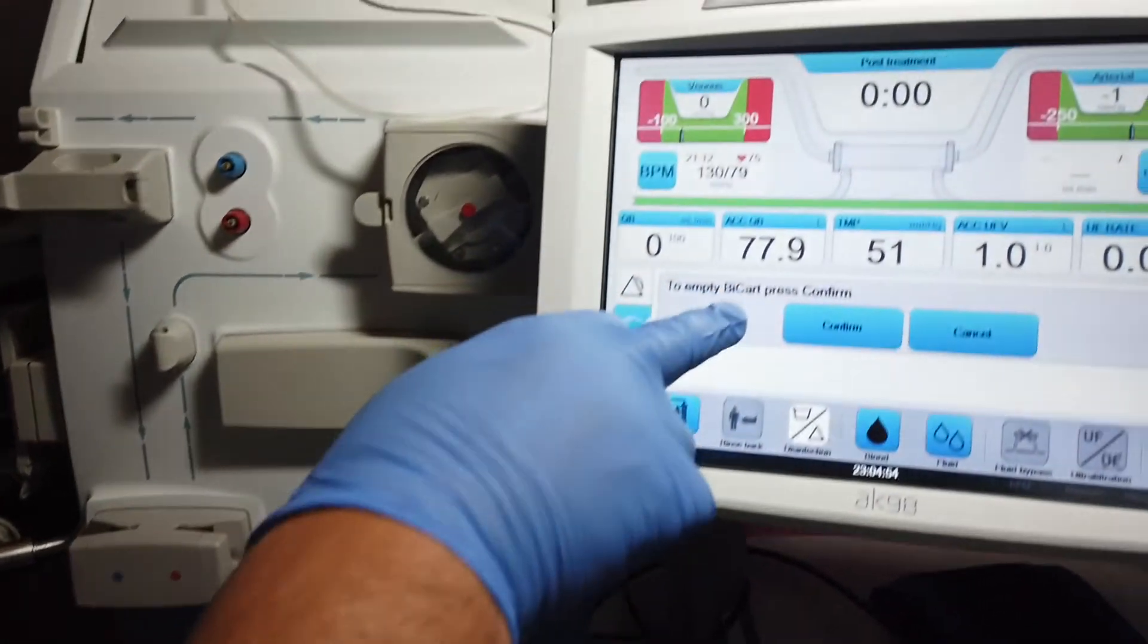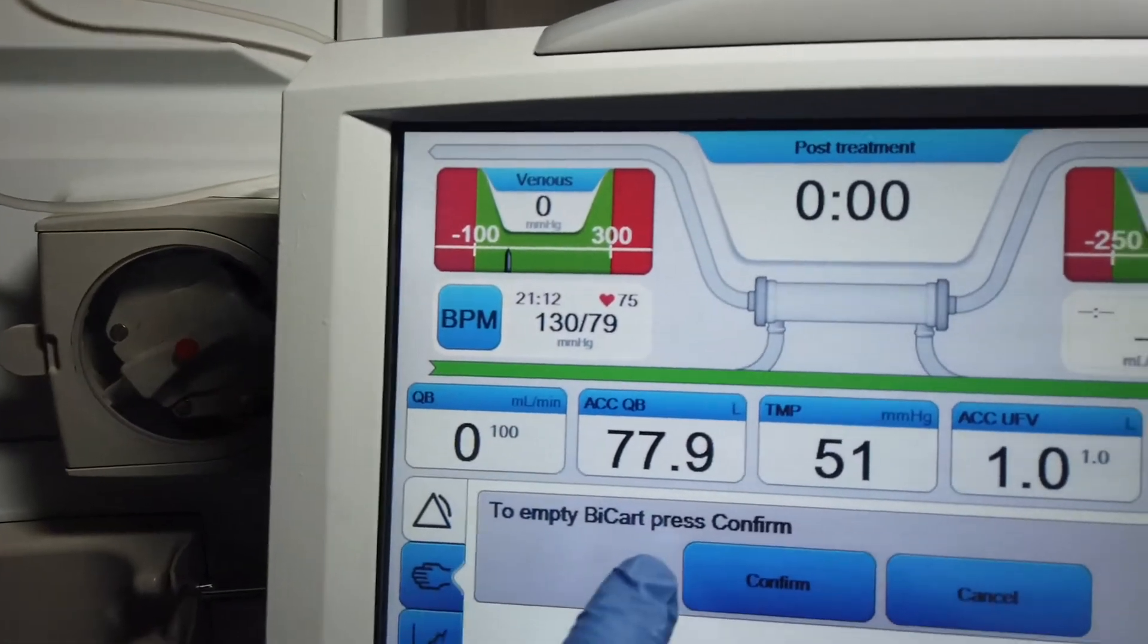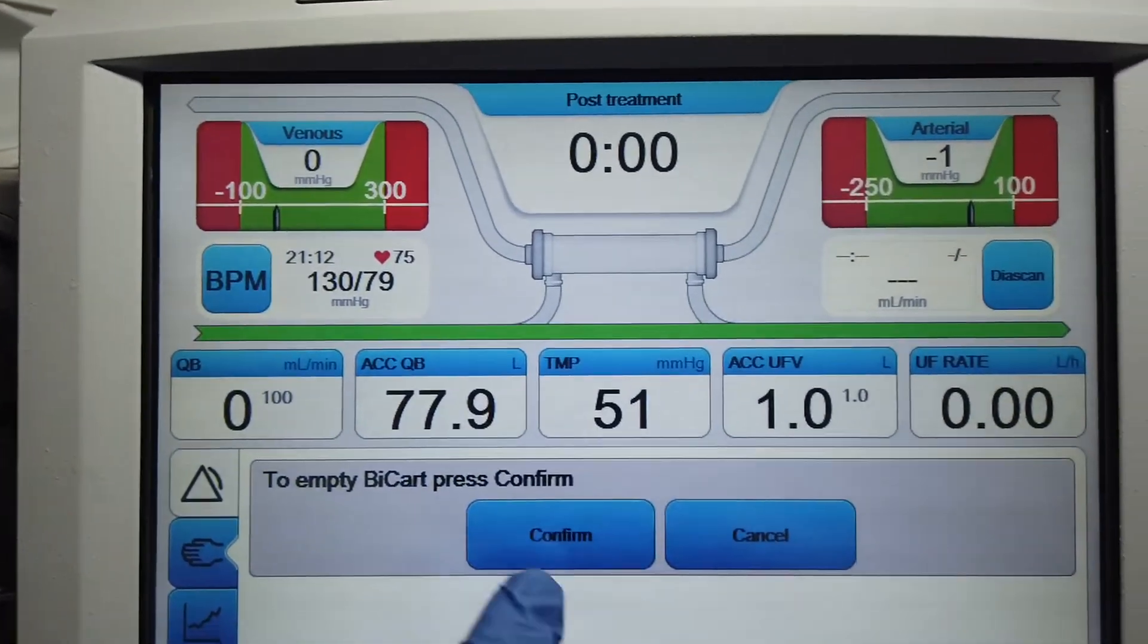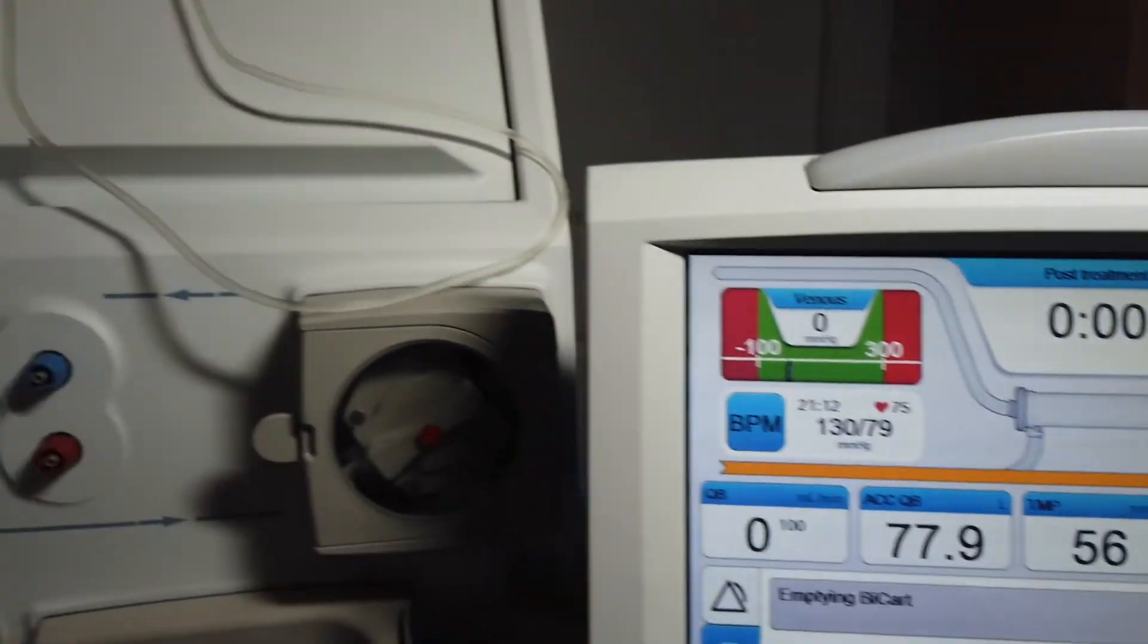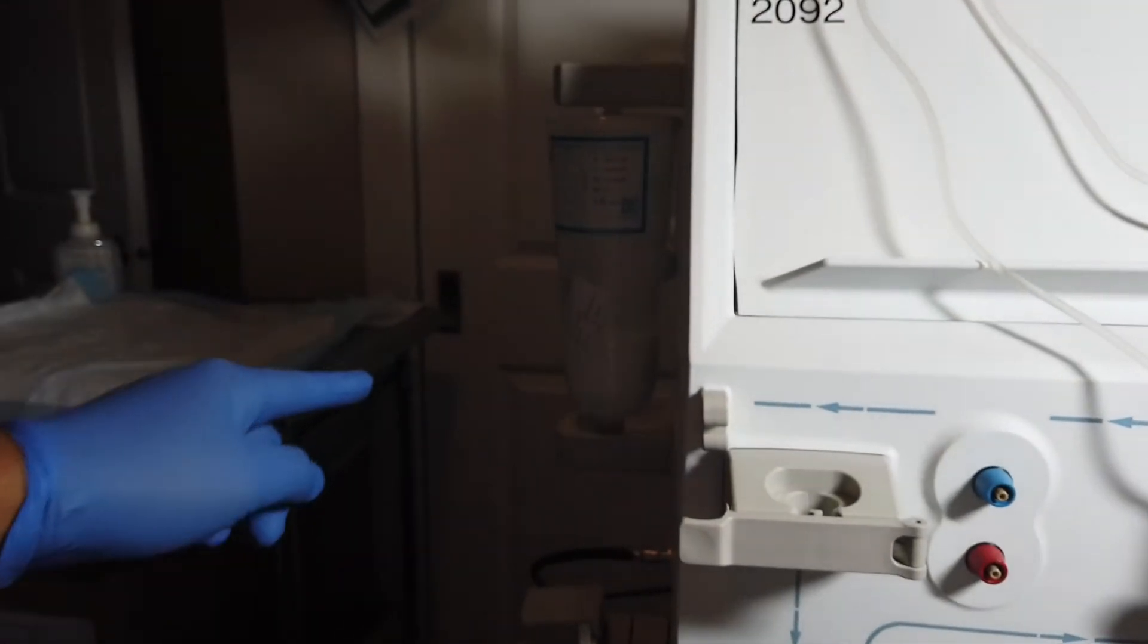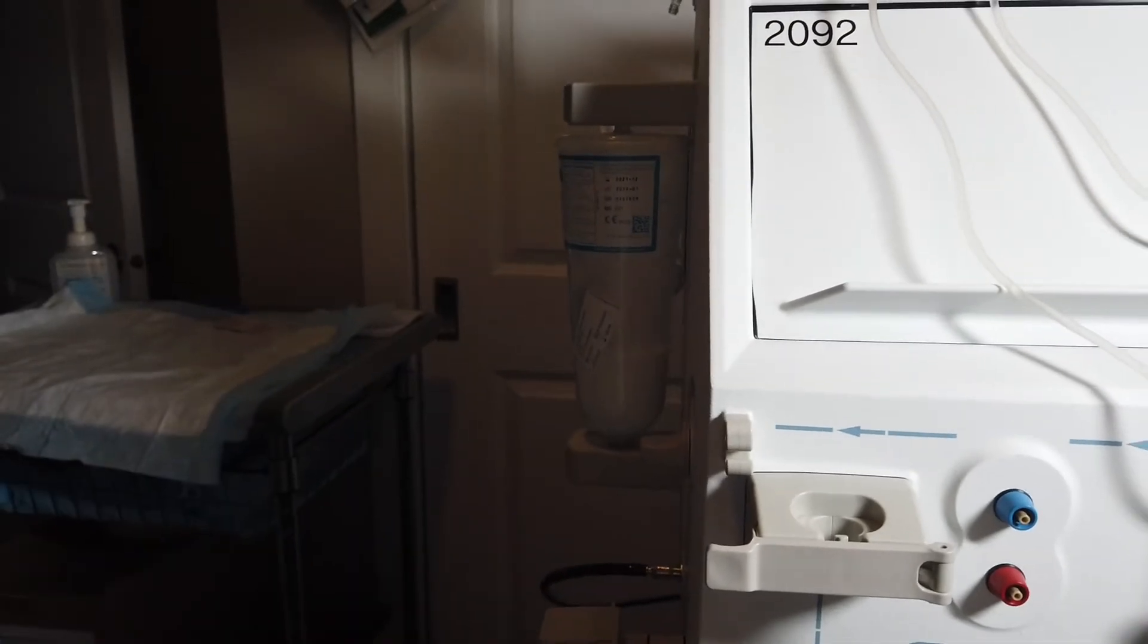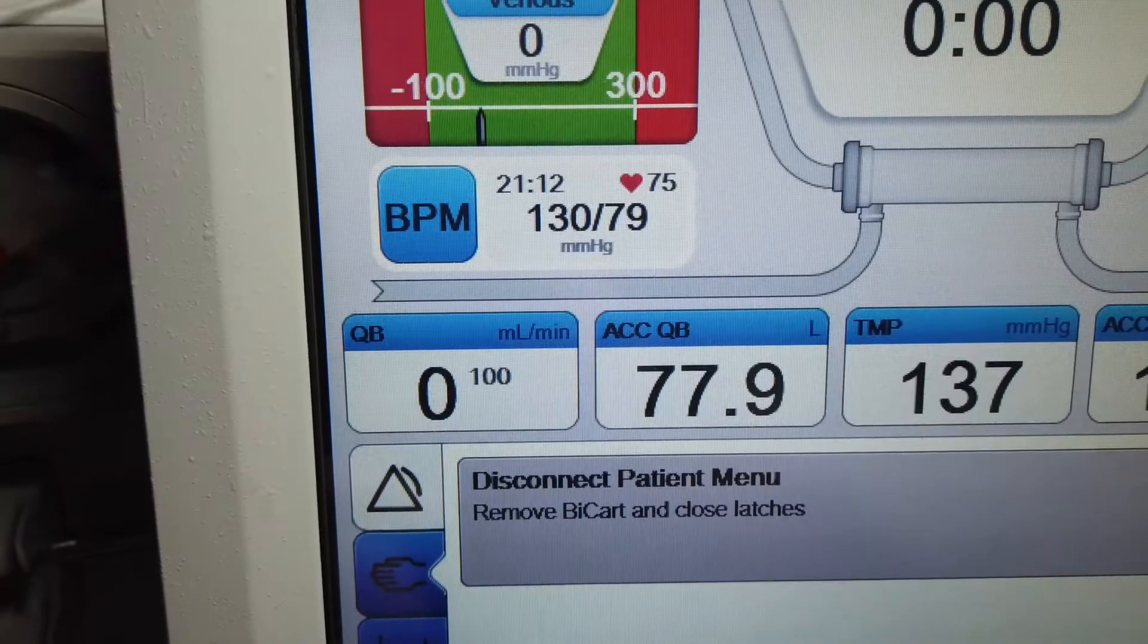After that is in, my screen should say to empty BiCart. Press confirm. I go ahead and confirm that. Now this is starting to empty out. While that is emptying out, I'll do the next preparation.